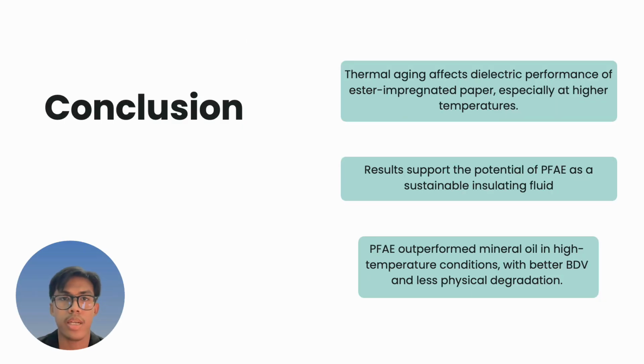In conclusion, the selected tools effectively support this project in evaluating the thermal aging effects on the dielectric properties. The impedance analyzer revealed how permittivity and tangent delta change across aging durations, while BDV tests confirm the electric endurance difference between PFAE and mineral oil. So this project demonstrates the strengths and limitations of each tool and highlights the importance of proper insulation material selection in high voltage transformer systems.